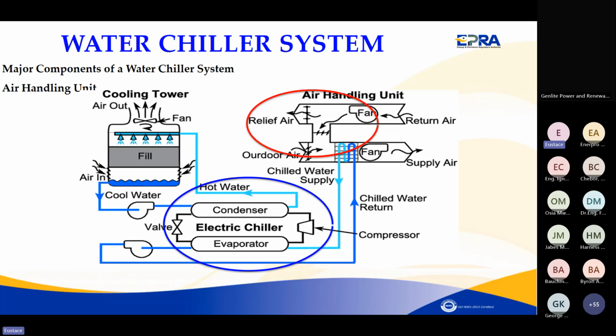What you need to establish in this case is whether the chiller is running the whole system efficiently, not to establish the EER. Even during the energy audits, you don't waste your time trying to establish the EER of the chiller system at this particular point. Because even when it was being established, you don't even consider things like the cooling of the condenser and so on, because it's in a well-controlled system. So most people can measure the power input, try to measure the temperatures of the refrigerants from the evaporator to the condenser and so on. That one won't give you much.